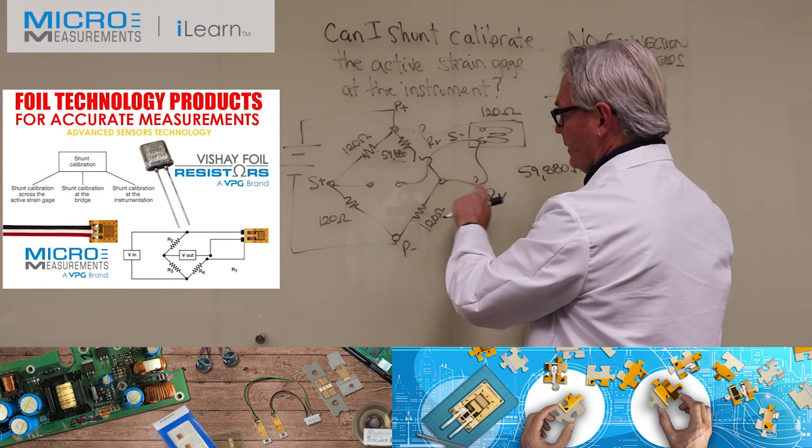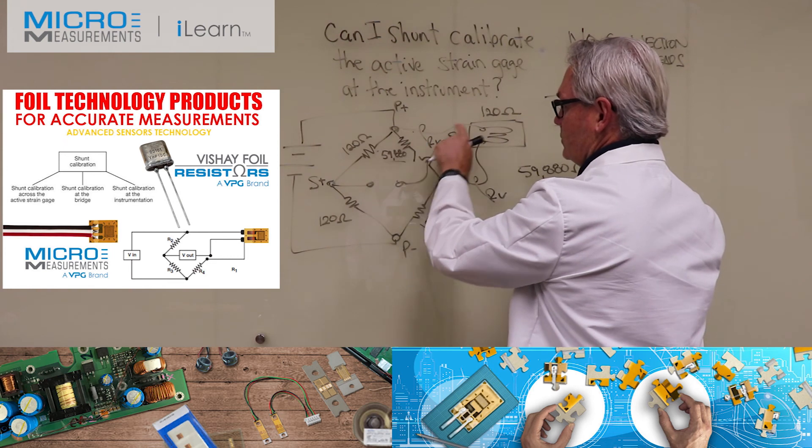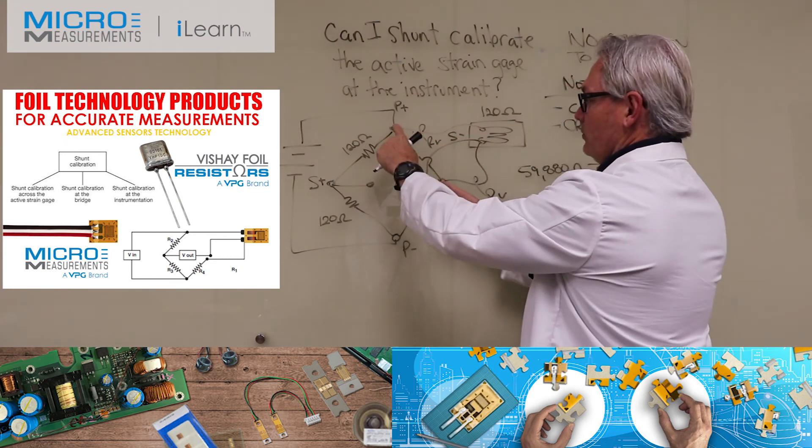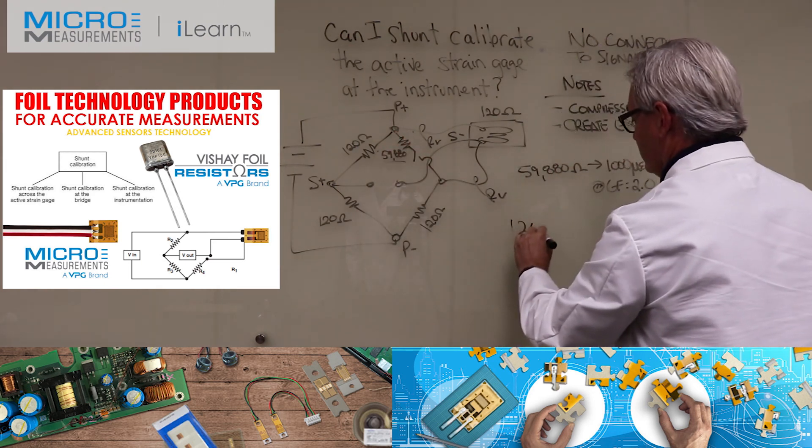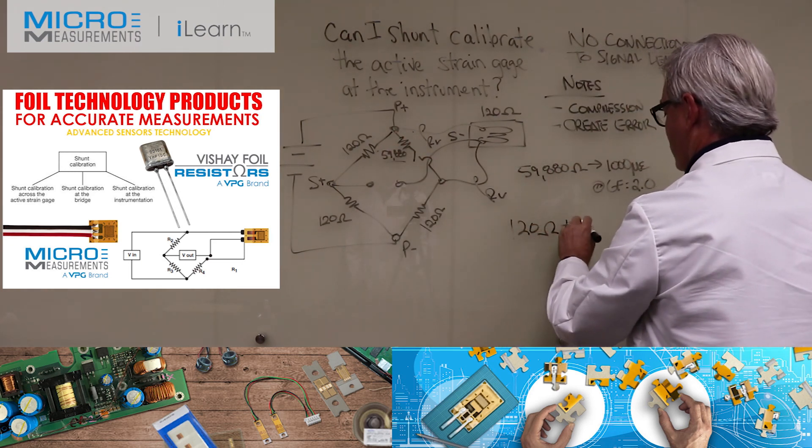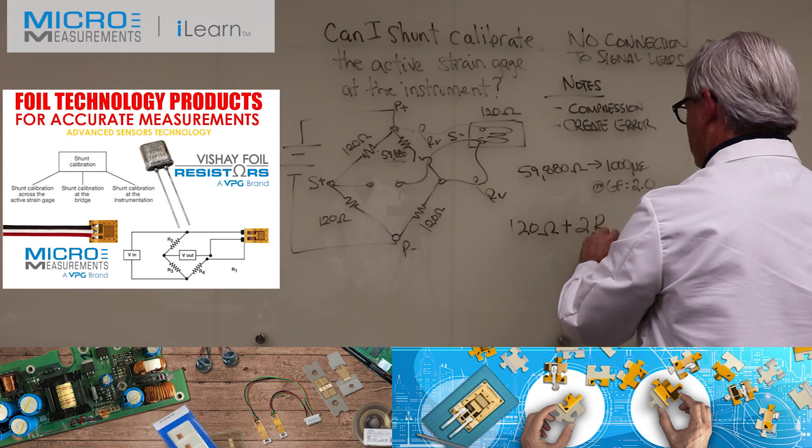In general it's a bad idea, and the reason it's a bad idea is the variability in the resistance of these two wires. Because now you're not calibrating across 120 ohms - you're calibrating across 120 ohms plus whatever two times R_sub_L is.